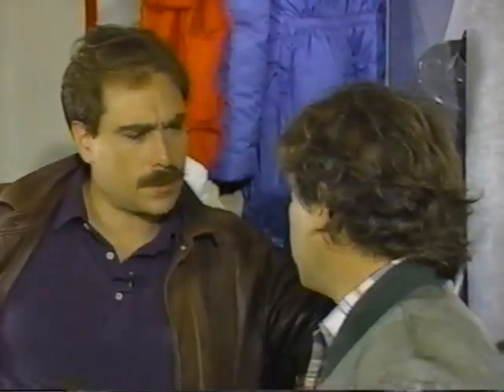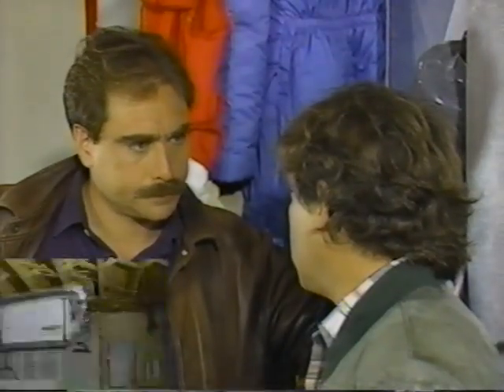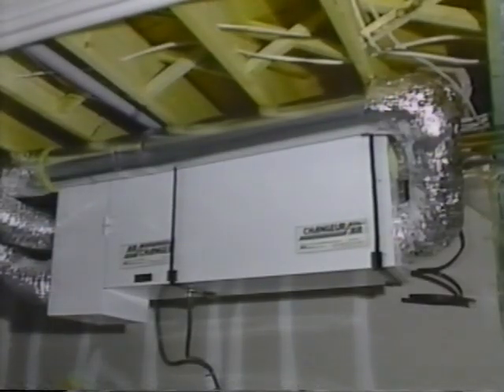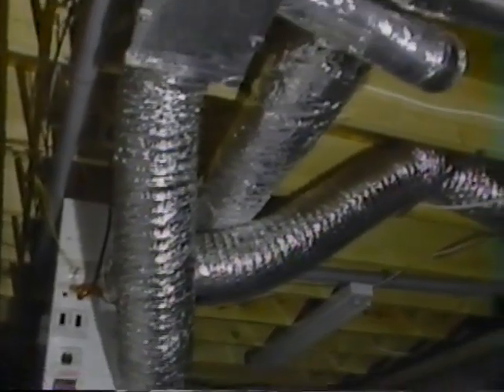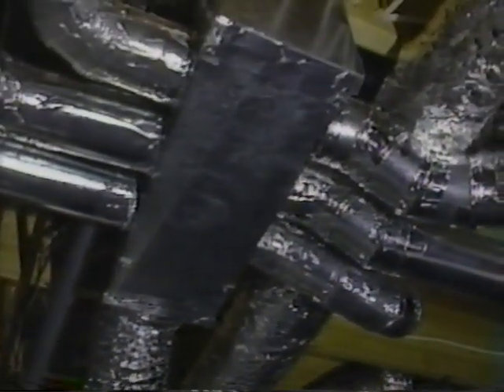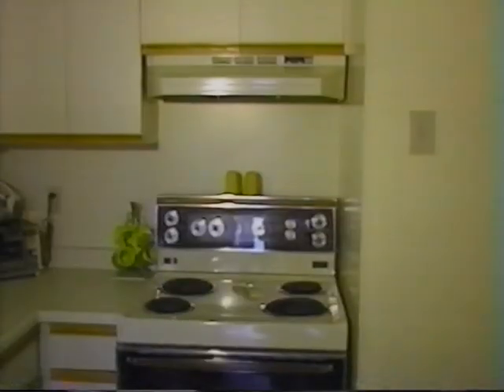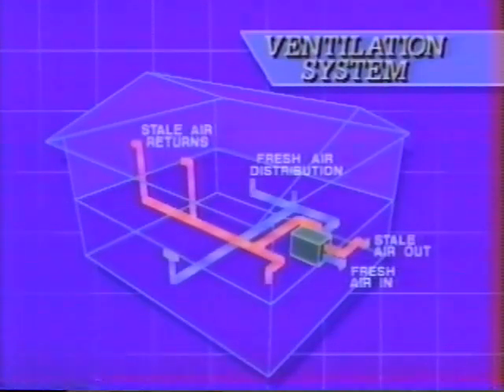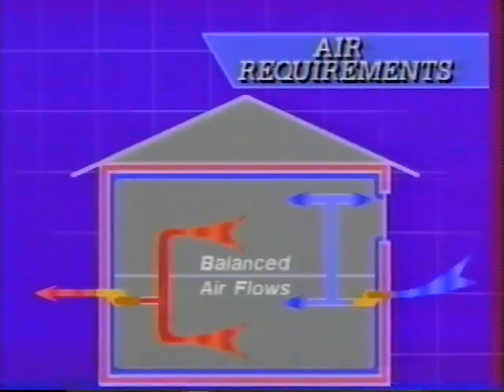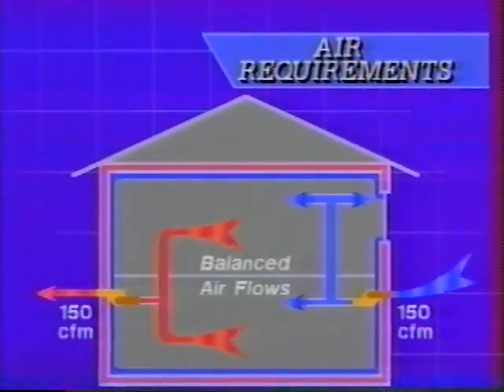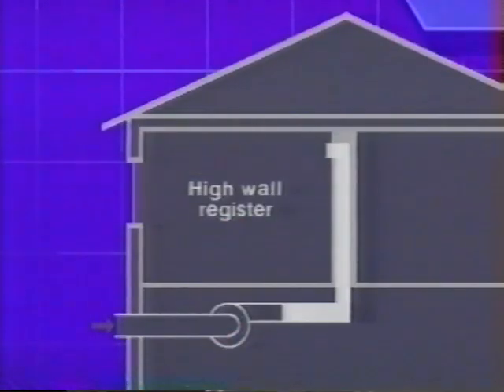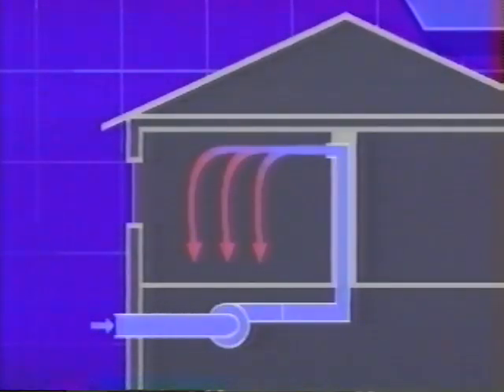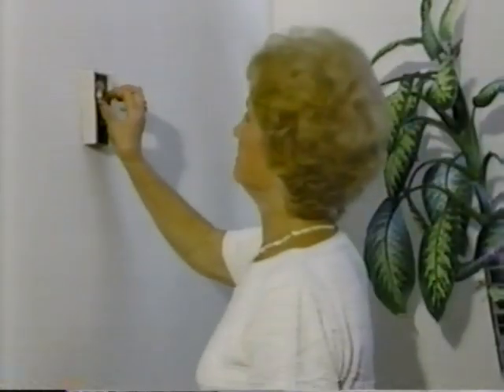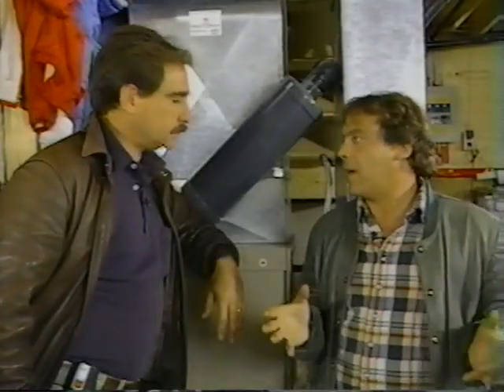While we're on the subject of ventilation systems, why don't we do a quick review? A main feature of the Better Built House is the incorporation of a mechanical ventilation system. The properly designed ventilation system will exhaust stale, humid house air from those areas of the house where it's generated, usually the bathrooms, kitchen, and laundry room. Fresh air will be provided in sufficient quantity and then delivered to each and every room of the house. The ventilation system should operate on a balanced basis, supplying and exhausting air at the same rate. Finally, the ventilation system of the Better Built House will provide fresh air in a manner which meets the comfort requirements of the occupants.